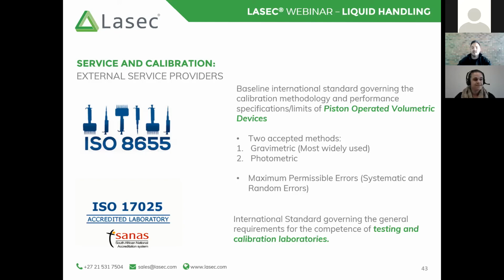All right, so also what this ISO standard does is it dictates what the maximum permissible errors are for certain pipettes. So this is basically for manufacturers that are making these pipettes, they need to ensure that all their pipettes are performing within these maximum permissible errors. Obviously, it is also up to the end user if they want to employ stricter limits on their pipette performance. They just need to make sure that their pipette is able to perform within such strict limits. So if you do have a certain criteria and you are sending your pipette in to be calibrated, you can mention what your criteria is, and thereby the pipette calibration technician can actually see if it is possible to reach those limits using your pipette, or whether a new or refurbished pipette might be necessary.